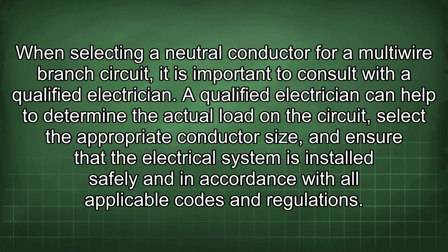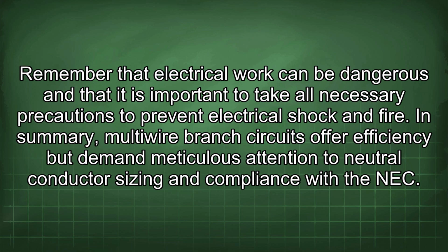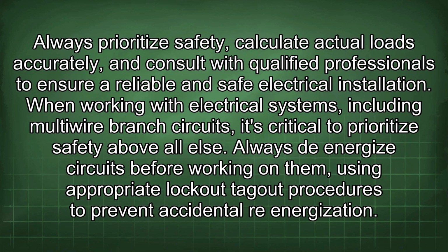When selecting a neutral conductor for a multi-wire branch circuit, it is important to consult with a qualified electrician. A qualified electrician can help to determine the actual load on the circuit, select the appropriate conductor size, and ensure that the electrical system is installed safely and in accordance with all applicable codes and regulations. Remember that electrical work can be dangerous and that it is important to take all necessary precautions to prevent electrical shock and fire. In summary, multi-wire branch circuits offer efficiency but demand meticulous attention to neutral conductor sizing and compliance with NEC.